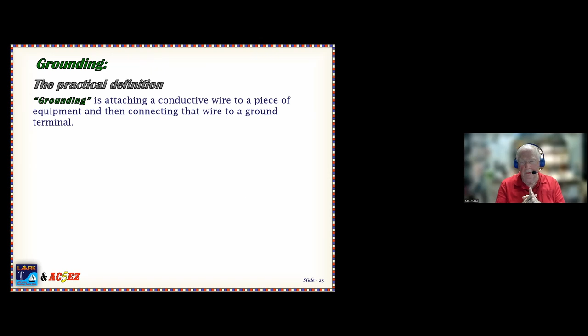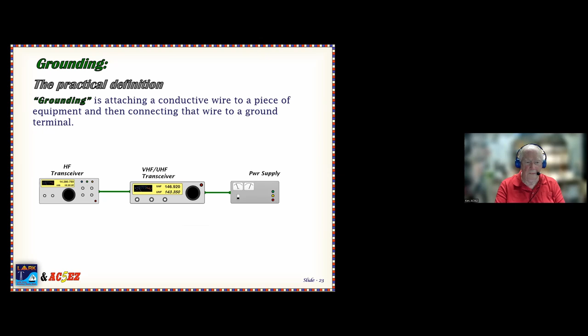Okay. All right. Here's our system again. Here's our three pieces of equipment. Now, bonding says connect all three of these pieces of equipment together with a wire. Okay. I have just satisfied that requirement for bonding. Now to ground, I'm going to connect all three of those to my ground wire. Okay. Well, a lot of us say, well, gee, that's kind of redundant. I don't need those extra wires. Why don't I just get rid of those? And that's okay for right now. We're just trying to satisfy the definitions. We have satisfied bonding and we have satisfied grounding. So far we're okay.